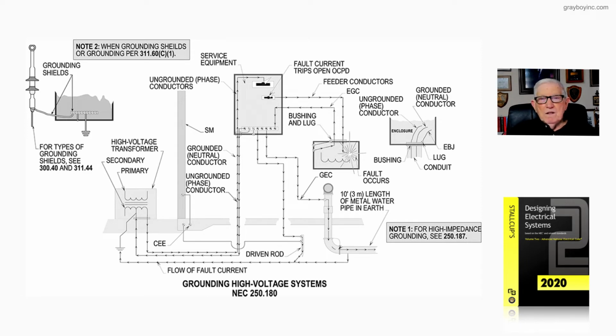250.102C1. The equipment grounds that you see, or I shouldn't say equipment grounds, pardon me, the grounding electrode conductors that are connected into the driven rod are sized from table 250.66. Or you would go to 250.66A. The table would be used to connect to the water pipe. Now make note that the table 250.66 is only used when you ground with a grounding electrode conductor to a metal water pipe or to the structural steel.